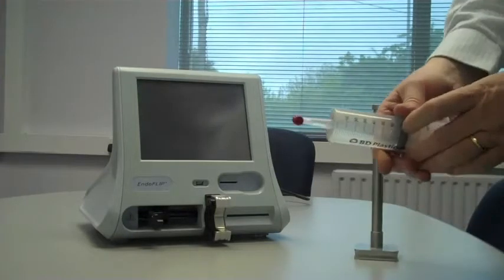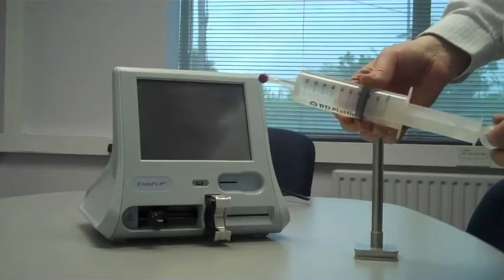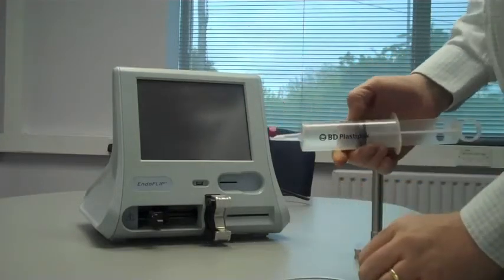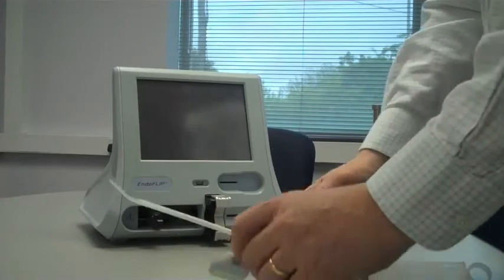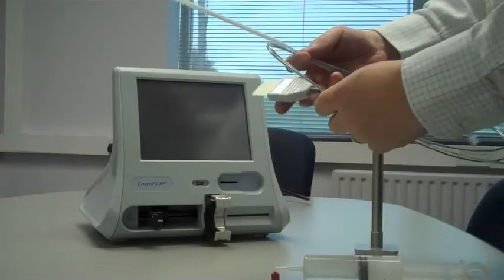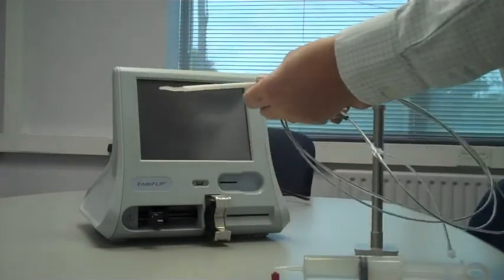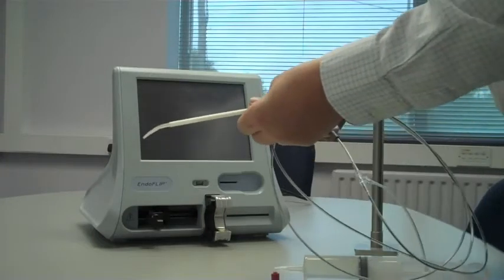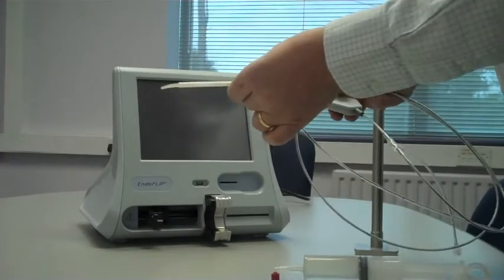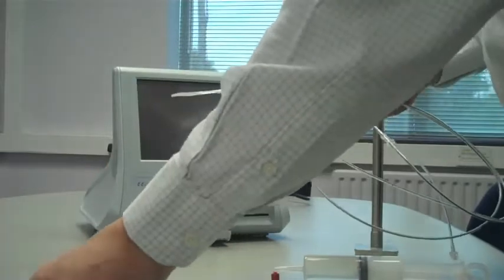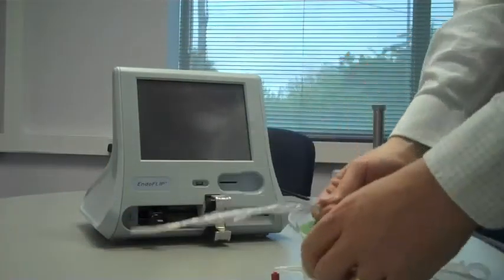The EndoFLIP catheter comes in two parts. There's a pre-filled syringe and the catheter itself. The catheter comprises a series of electrodes which allow cross-sectional area to be measured, and the first thing you want to do is remove the protective sleeve from the catheter.